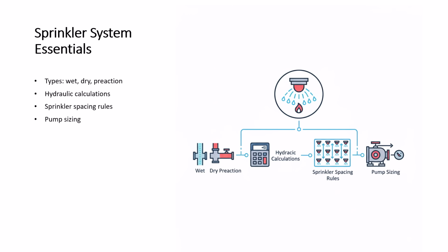Just as an example, if we have an area of normal or hot temperature, we will be using wet risers there. That will be our wet sprinkler system. But if we are going to install our sprinklers in an area that is very cold, we are not allowed to use the wet sprinkler system. This is because the water inside the pipes will freeze, and if there is an unusual event of fire, our system is not going to activate to prevent the fire, because the water inside the pipeline is already frozen. So we are going to use a dry system there.